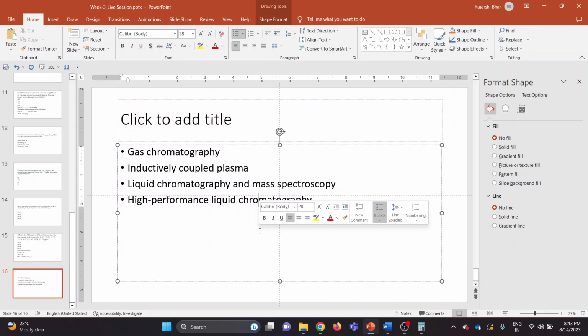So based on those signature emissions, the detector identifies which element is present, and based on the intensity of those emissions, the concentration or the amount present in a certain mass is determined. So that is how basically an inductively coupled plasma, or ICP, works.